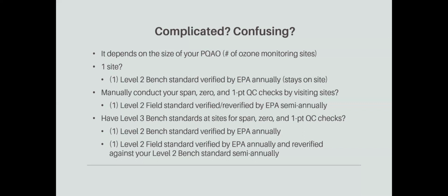Do you have a couple sites where you manually conduct your zero span QC checks by visiting the sites every 14 days? Well, then one level 2 field standard will probably work for you, except EPA will need to see that semi-annually. Or do you have a bunch of level 3 bench standards that sit at your site and run automated checks for your span QC checks? Well, you might have one level 2 bench standard that's verified annually, and then one level 2 field standard that you take to the field to challenge those level 3s.